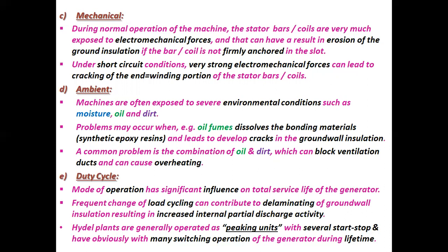E. Duty cycle. The mode of operation has significant influence on the total service life of the generator. Frequent change of load cycling can contribute to delaminating of ground wall insulation, resulting in increased internal partial discharge activity. Hydel plants are generally operated as peaking units with several start-stops, and obviously with many switching operations of the generator during its lifetime.